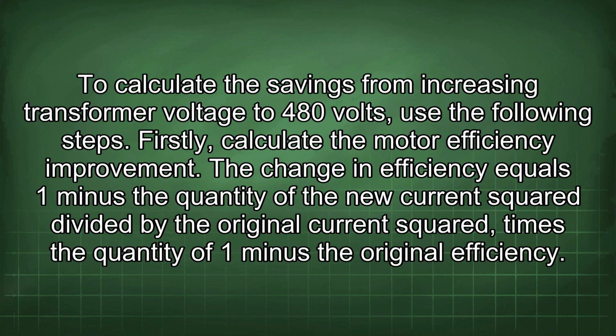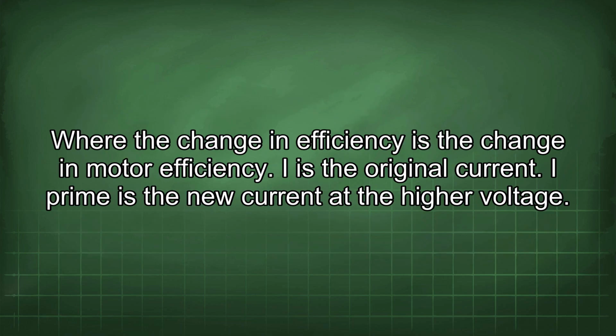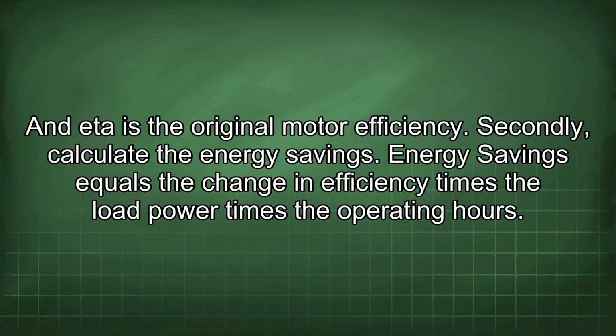To calculate the savings from increasing transformer voltage to 480 volts, use the following steps. Firstly, calculate the motor efficiency improvement. The change in efficiency equals 1 minus the quantity of the new current squared divided by the original current squared, times the quantity of 1 minus the original efficiency, where the change in efficiency is the change in motor efficiency, I is the original current, I prime is the new current at the higher voltage, and eta is the original motor efficiency.